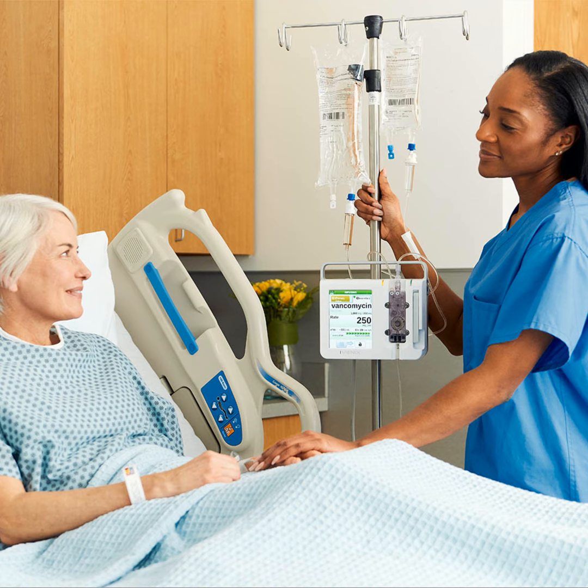And the tubing and the pump should work in harmony. So the pump should recognize the type of tubing that's loaded into the pump. It should provide workflow guidance based on the type of tubing. So if you put blood tubing into the pump, it helps you deliver blood. All of this is really creating safety checks along the way. And this, along with the design of the tubing itself, helps protect against free flow conditions, and this is always a continued cause for patient harm. So the newest, most advanced infusion pumps should be designed to not even allow free flow to occur.